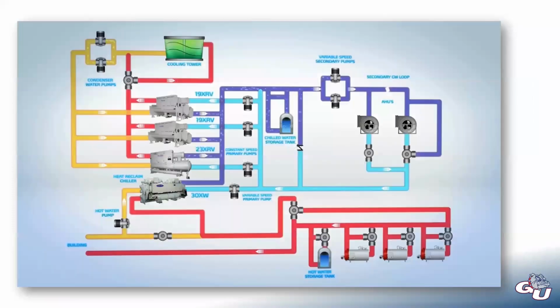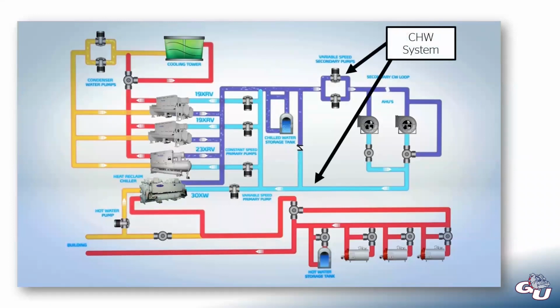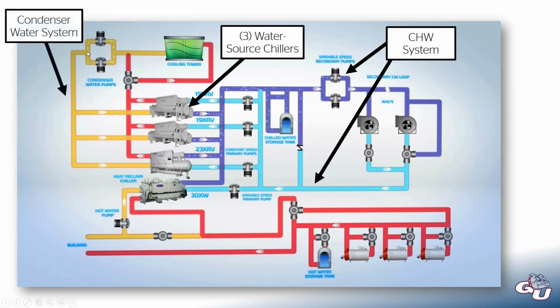So what would that look like in practice? I realize this is a lot. There's a lot going on in this diagram, but let's walk through the primary components. We have our chilled water system. So this is pumping chilled water through some air handlers, through some chilled water coils, wherever that chilled water is needed. And then we have 3 water source chillers, and you can tell they're water source because on this side, they're connected to a condenser water system. You have your cooling tower. So as these 3 chillers are running, they're pulling heat from this side, rejecting it into the condenser water, which then goes into the cooling tower where it gets rejected outside.